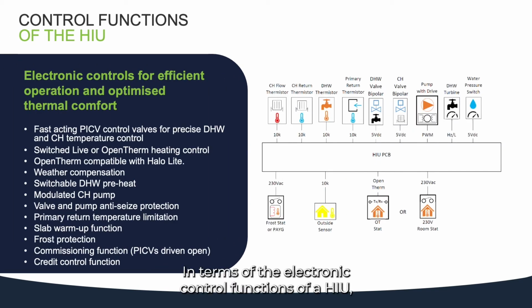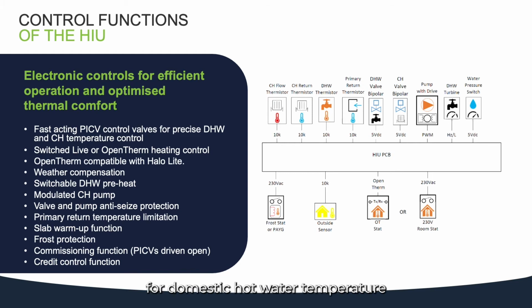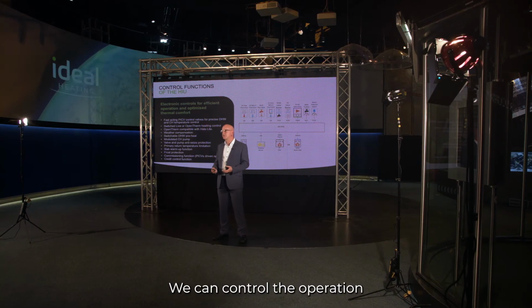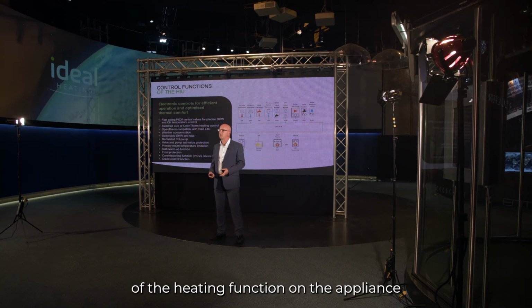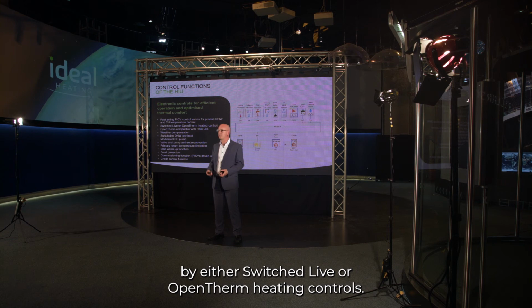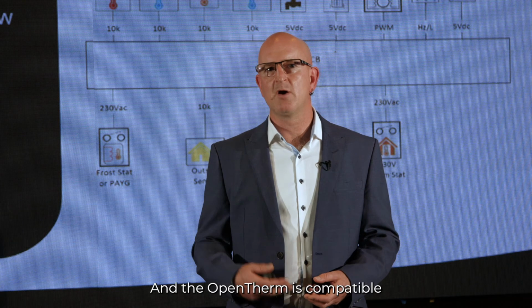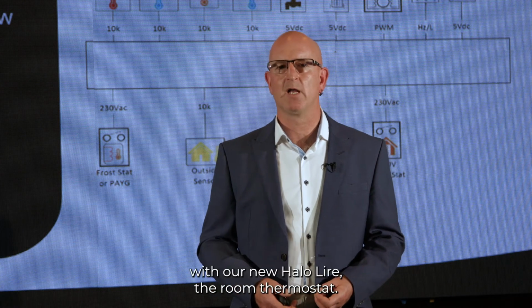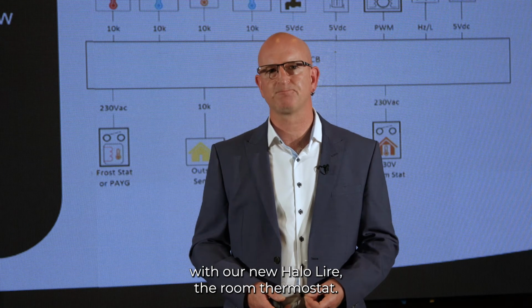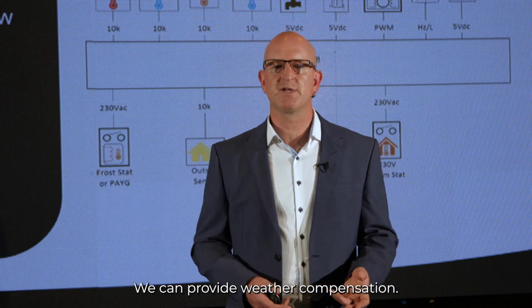In terms of the electronic control functions of a HIU, we've got fast-acting pressure-independent control valves. These give us precise control for domestic hot water temperature and central heating temperature. We can control the operation of the heating function on the appliance by either switched live or OpenTherm heating controls, and the OpenTherm is compatible with our new Halo Lite room thermostat. We can provide weather compensation.